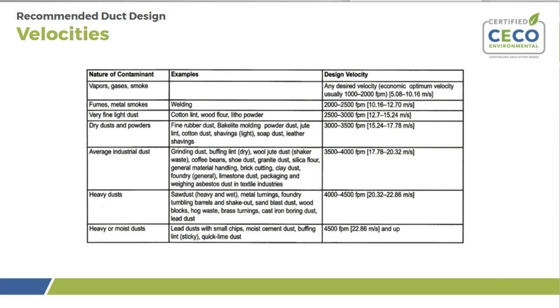For your average industrial dust, 35 to 4,000. We typically design it around 4,000 if it has what we consider a dust source. For a heavy dust, where you're going to get chunks of wood or particulate that's sand in nature, you want to go higher so you don't have dropout, because even though the system may convey heavier chunks of particulate, they tend to drop out and cause problems for you in the future in that ductwork.